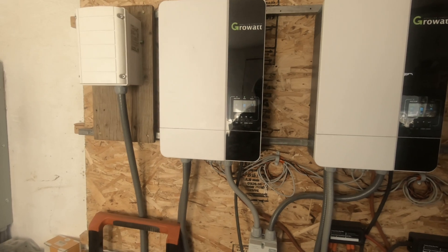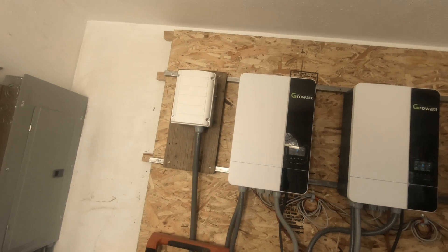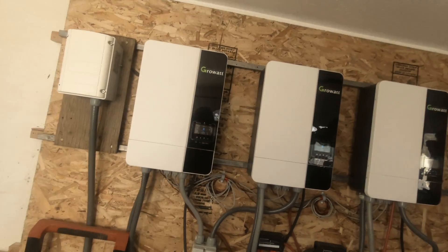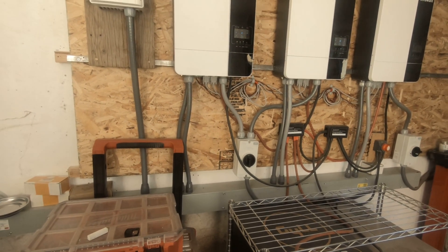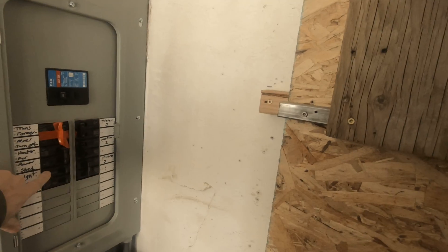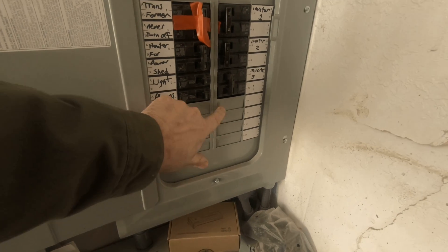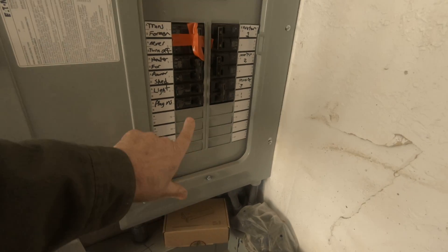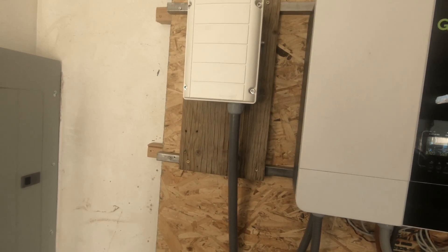I saw the video with Watts 24-7. What he did was he loaded one leg of the power — he put all of his heaters on one leg, this one and so forth — ignoring the other leg. He intentionally imbalanced the load to where it overloaded the auto transformer.